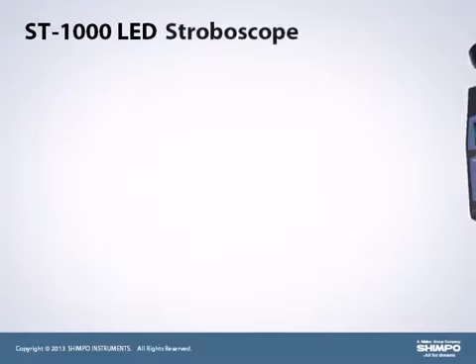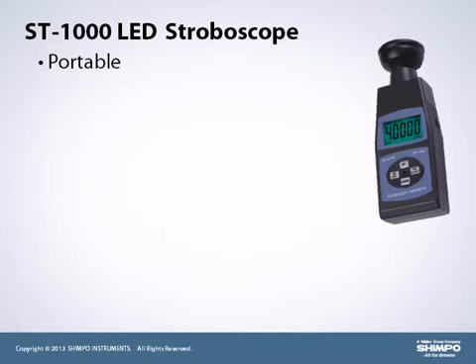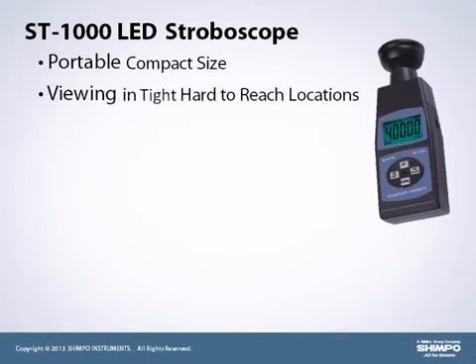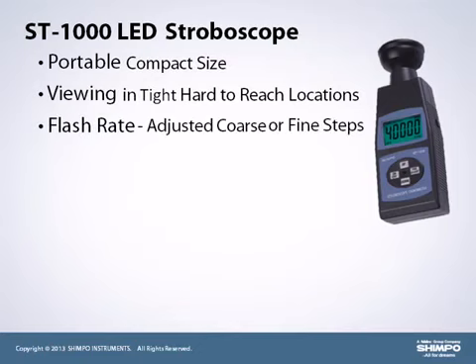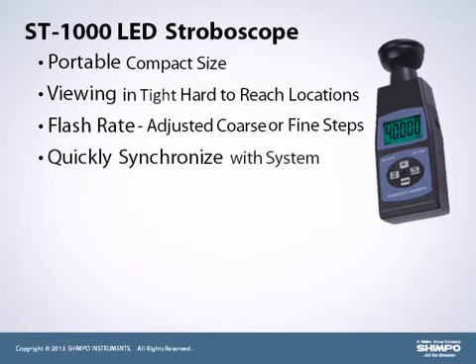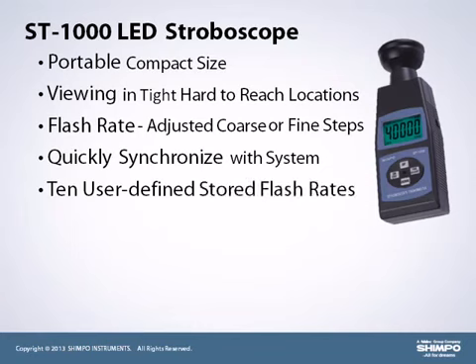The ST-1000 LED stroboscope offers complete portability with its compact size, allowing equipment viewing in tight, hard to reach locations. Its flash rate can be adjusted in either coarse or fine steps, allowing the operator to quickly synchronize with the speed of the system under view. Ten user-defined stored flash rates can automatically adjust the flash speed, allowing the operator to save additional time on previously tuned processes.